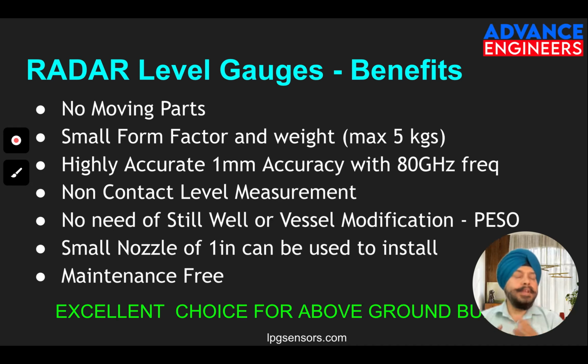But here radars can give you accuracy of 1 mm - that's a documented fact. So don't worry about the accuracy, because I hear these kinds of questions from a lot of users that servo gauge accuracy is very high and radar gauge accuracy is very low. But actually both are the same. If a servo gauge is not well maintained, you will see the accuracy going between 5 to 6 inches also. So end of the day, it's how you maintain that machine or instrument - that is the way it is going to work.